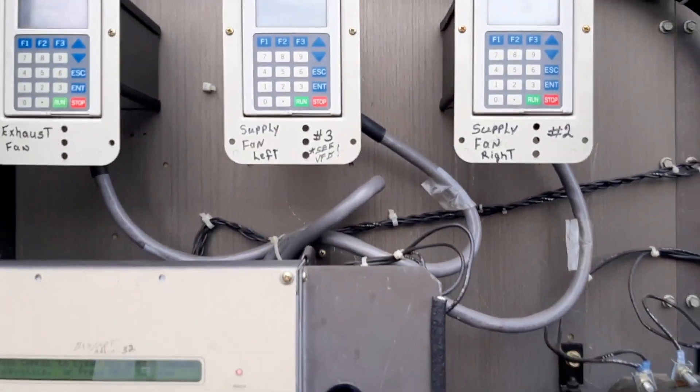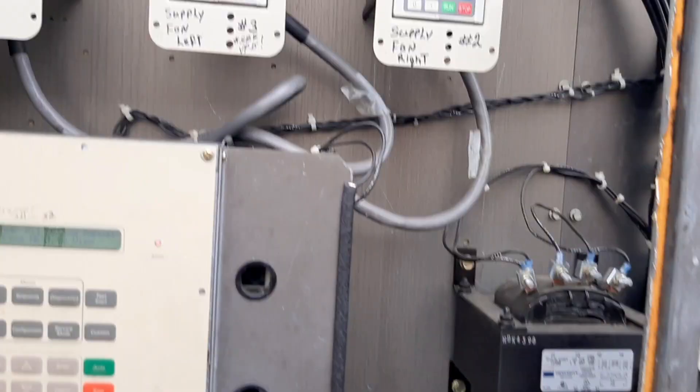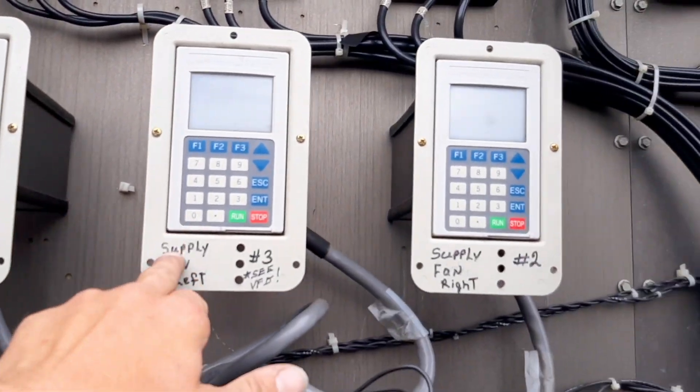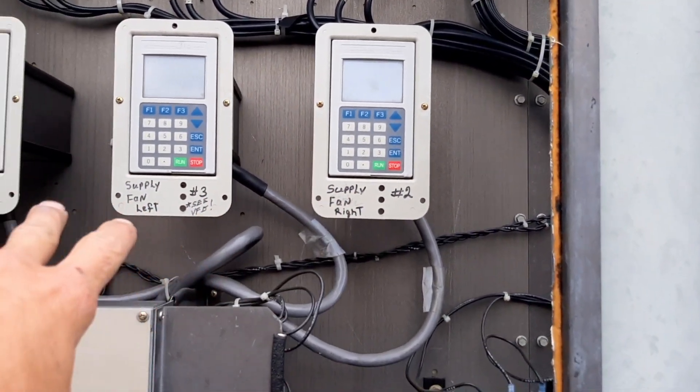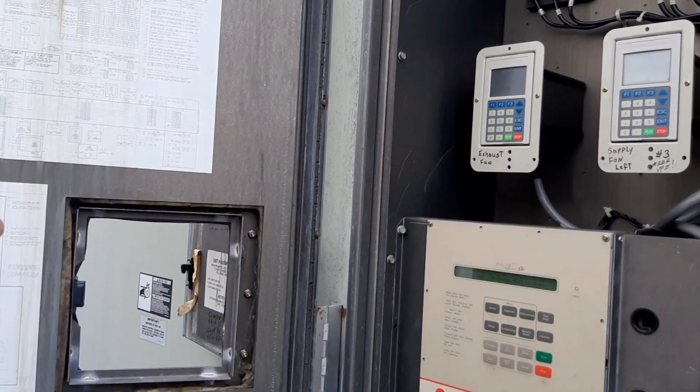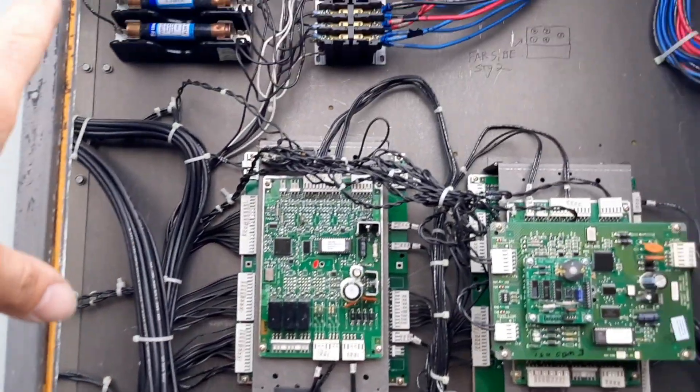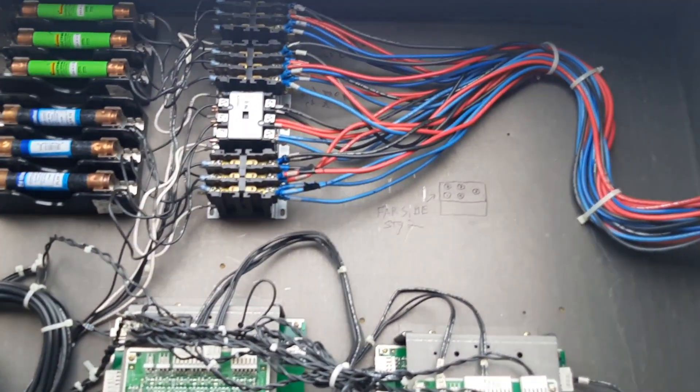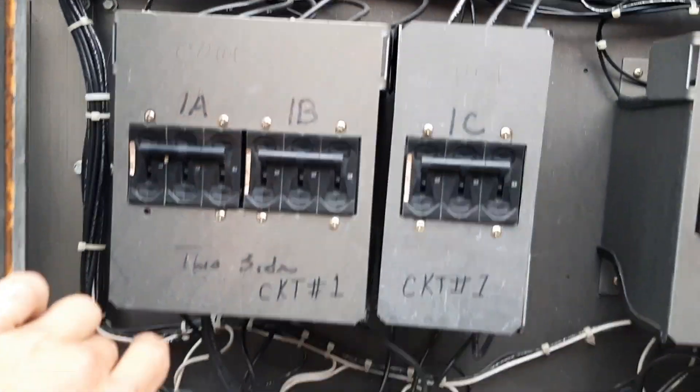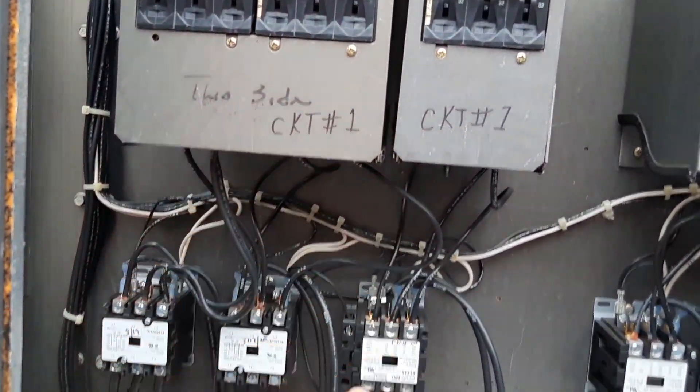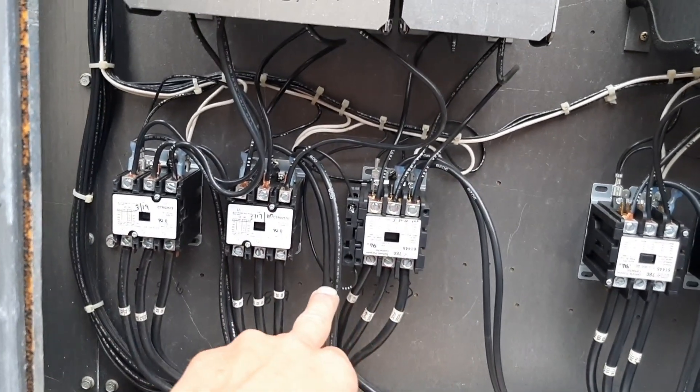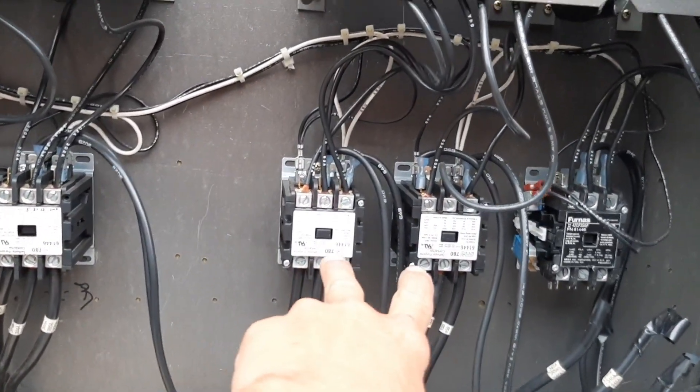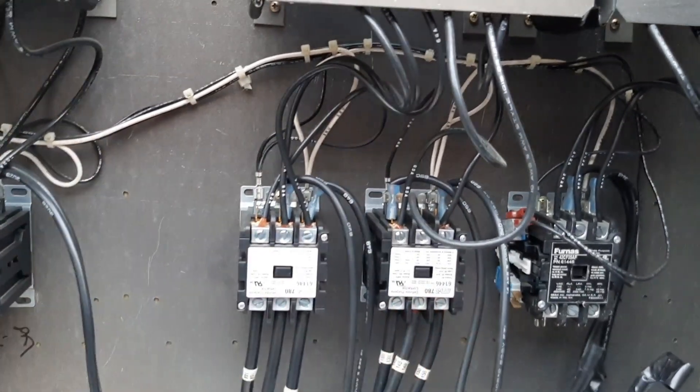Everything looks normal in our control panel. These are just the remote modules, they don't work. The VFDs for all the drives are on the back. You can see evaporator motor contactors, fuses. We've got all three compressors on circuit one running, and the other two have cycled off.